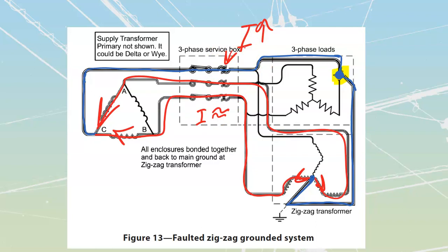The faulted line itself is going to trip. It's going to blow that fuse off sooner than it should blow the fuses off of either of these two, because both of those ones, when we take a look at them, we see that they are carrying through smaller values of current.